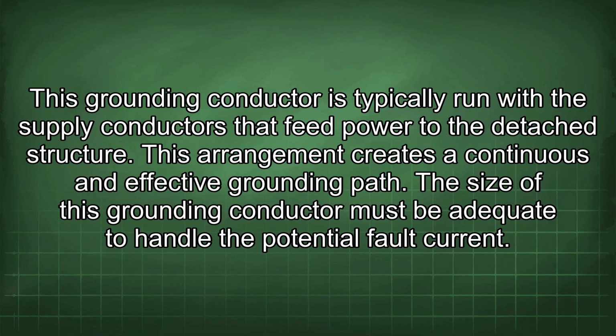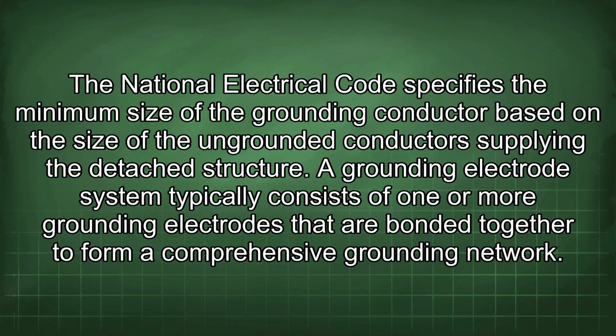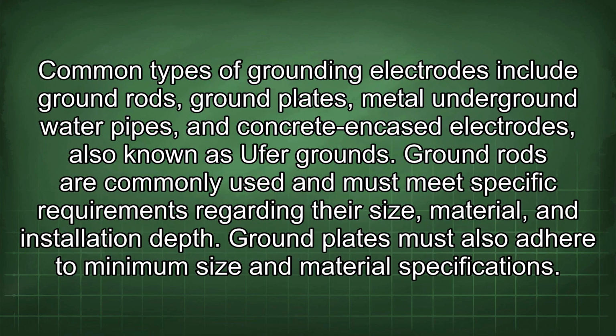The size of this grounding conductor must be adequate to handle the potential fault current. The National Electrical Code specifies the minimum size of the grounding conductor based on the size of the ungrounded conductors supplying the detached structure. A grounding electrode system typically consists of one or more grounding electrodes that are bonded together to form a comprehensive grounding network. Common types of grounding electrodes include ground rods, ground plates, metal underground water pipes, and concrete encased electrodes, also known as Ufer grounds. Ground rods are commonly used and must meet specific requirements regarding their size, material, and installation depth. Ground plates must also adhere to minimum size and material specifications.